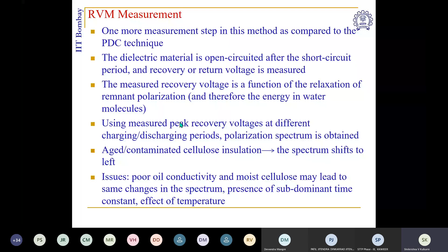So this is what I was saying. For polarization and depolarization currents, only the first two steps are there, charging and discharging, so you get the polarization current and depolarization current. If you are also working on the recovery voltage method, then you have one more step in which you measure the recovery voltage. Here you are applying the step voltage. In the second step you are short circuiting. In the third, you are open circuiting and measuring the recovery voltage. This recovery voltage is due to some polarized molecules on account of moisture, so the recovery voltage is indicative of moisture inside the insulation.